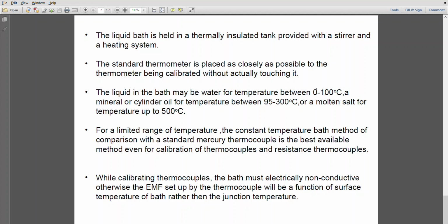While calibrating thermocouples, the bath must be electrically non-conductive. Otherwise, the thermo EMF generated between the hot and cold junction will be a function of the surface temperature of the bath rather than the junction itself. That's something we need to keep in mind.